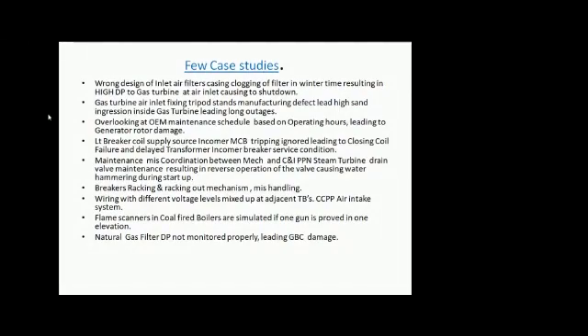And coming to the electrical wiring part, this is another issue, with different voltage levels of cables. Suppose I have an electrical cable of 230 volts and we have 24 volt DC. This wiring should never be terminated very near, adjacent. This mistake happened in one of my power plants, and when there is moisture, there can be a small carryover of charge from one terminal to the other terminal. Because of that, there used to be faults. So while doing wiring maintenance, while doing engineering, this should be seen to. After seeing these things, many developments have come. Now we have separate cabinets and marshalling racks, separately for AC and separately for DC. All those things are happening. But people have to take care of this kind of issue also when they are doing the maintenance.